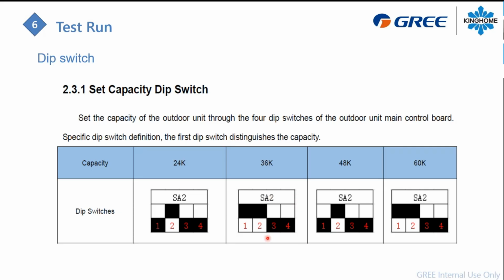If you have installed a 2-ton case coil and you want to run the outdoor unit as a 2-ton, you will need to move dip switch number 1 to the off position. So now dip switch number 1 acts as your capacity dip switch. By default, it's on for this kind of cabinet. If you need a lower capacity, you put it off. For the other cabinet, the 4 and 5-ton, by default it's on to act like a 5-ton. If you need to make it a 4, you just push it off. So that's dip switch number 1.